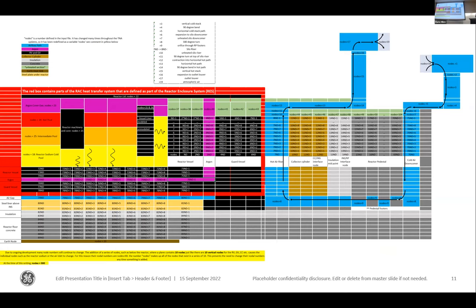The nodalization of the system is complex. We have airflow coming in, down the downcomer, through some orifices on the bottom, and up where it gets heated — that's where the driving air movement comes from — and out to the atmosphere. Heat flows from the cold pool; in steady state we hold the walls at a specific cold pool temperature. In the transient we open that up: heat generation happens in the hot pool, which flows through heat exchangers to the cold pool, with energy exchange through conduction, radiation, and convection through the reactor vessel and guard vessel.